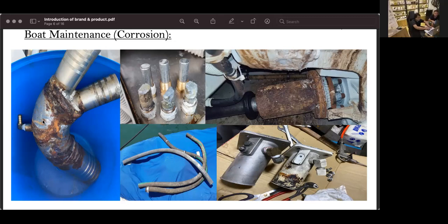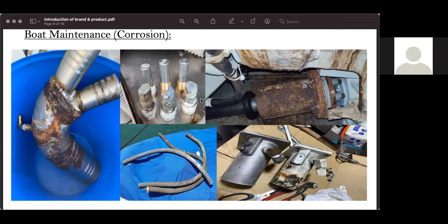It does have corrosion and leaking, quite often things that could happen. So throughout the surface we always check. This is another thing that we try to check for our starter issues, it's very common. Also, we can see we have some zinc anode, it's a must to replace. It really depends on the factory, some products we've seen recommend replacing every 3 months, some say every 100 hours.